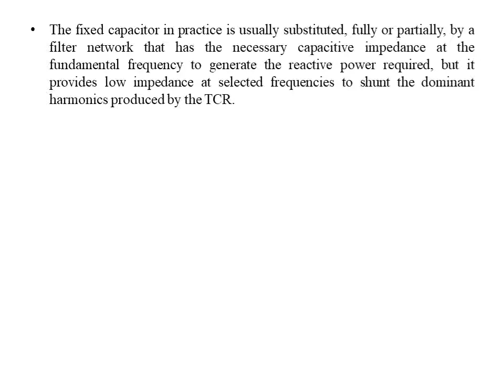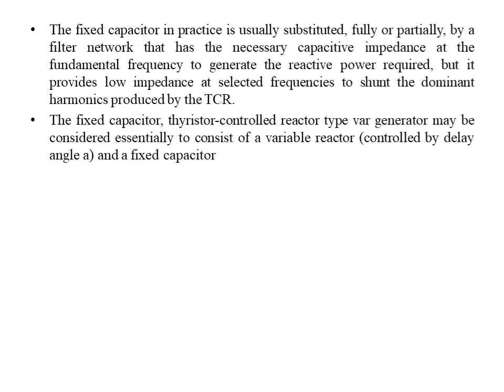That is nothing but this capacitor, that is permanently connected capacitor, eliminates the harmonics which are generated by back to back connected thyristors or thyristor controlled reactor. The fixed capacitor thyristor controlled reactor type VAR generator may be considered essentially to consist of a variable reactor and a fixed capacitor. So that's why the name is given as FCTCR, that is fixed capacitor and thyristor controlled reactor. The reactance or impedance of the line will be controlled by controlling the thyristors, but the capacitor will remain fixed or constant.